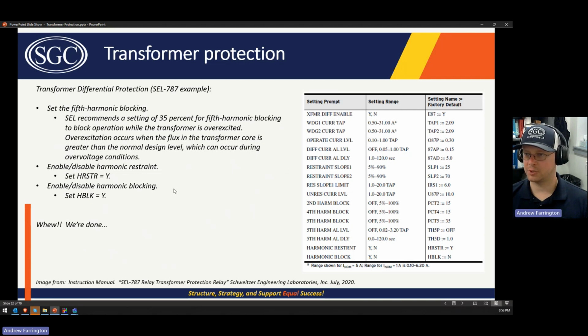I wish I could talk about it more. The fifth harmonic blocking, that's for over excitation. Basically, it's volts per hertz protection. I just don't have time to talk about it more in detail. It's not on the homework. So in this case, we would enable the harmonic restraint and enable the harmonic blocking, per the relay manufacturer's recommendations. And phew, we're done. We've set our transformer microprocessor-based differential relay.